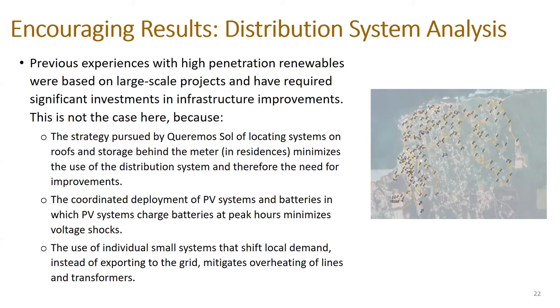So the long and short of this is that this isn't a completely perfect solution in the sense that there are still mitigations that must take place, but by shifting local demand, by putting the resource where the demand is, we mitigate the overall use of the distribution system, and we mitigate the inherent problems that typically go along with PV systems when they're applied in this fashion. So it's both the location and the nature of the systems that really resulted in the very encouraging results that we wound up with.